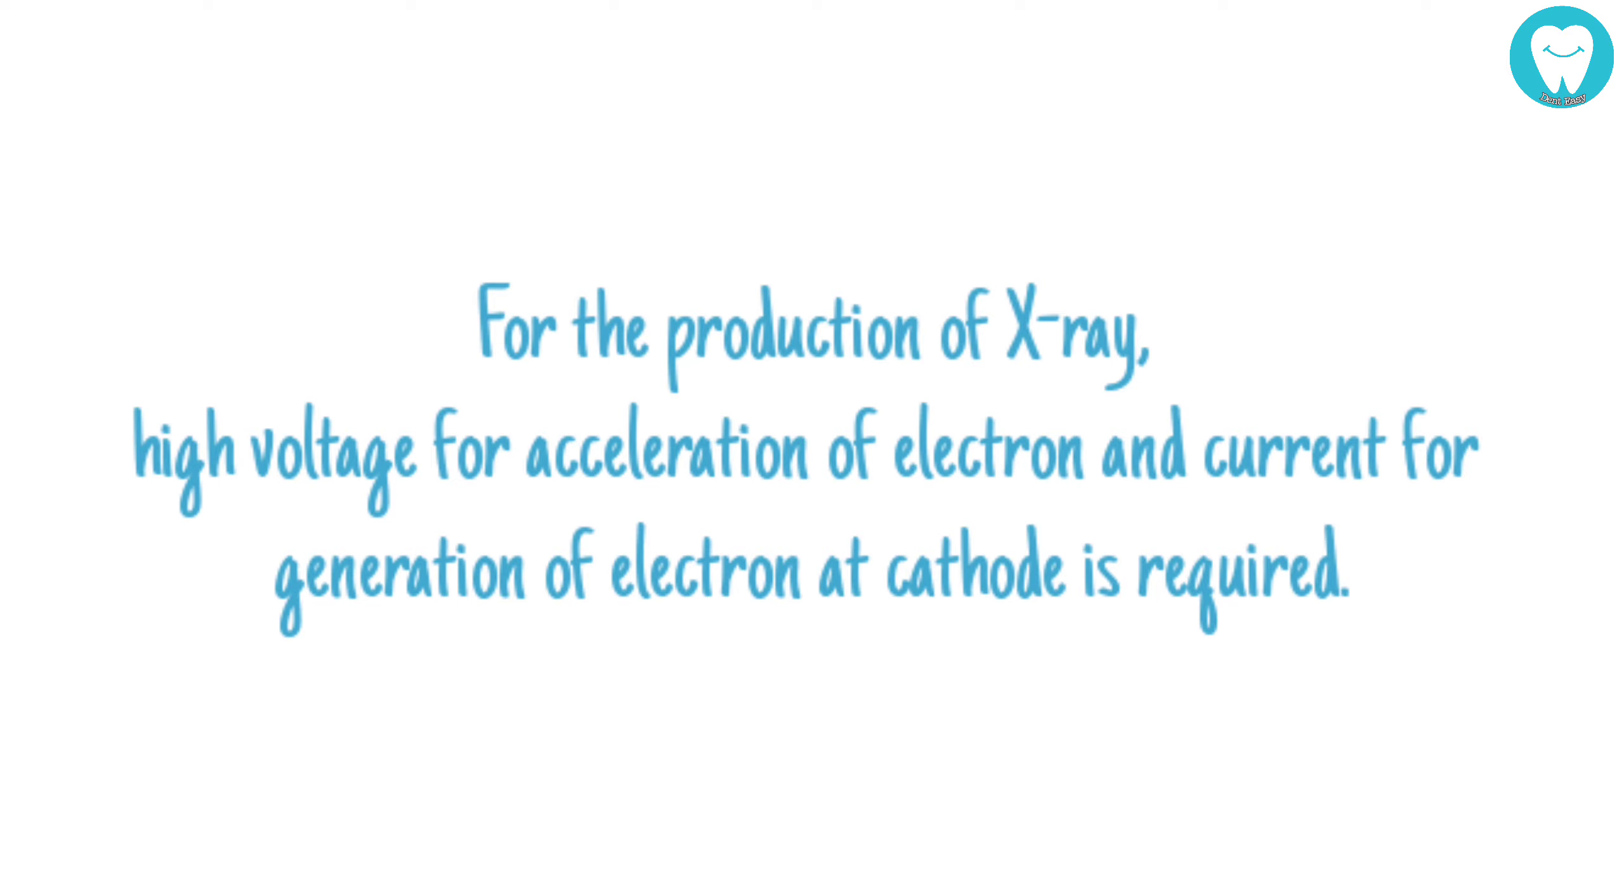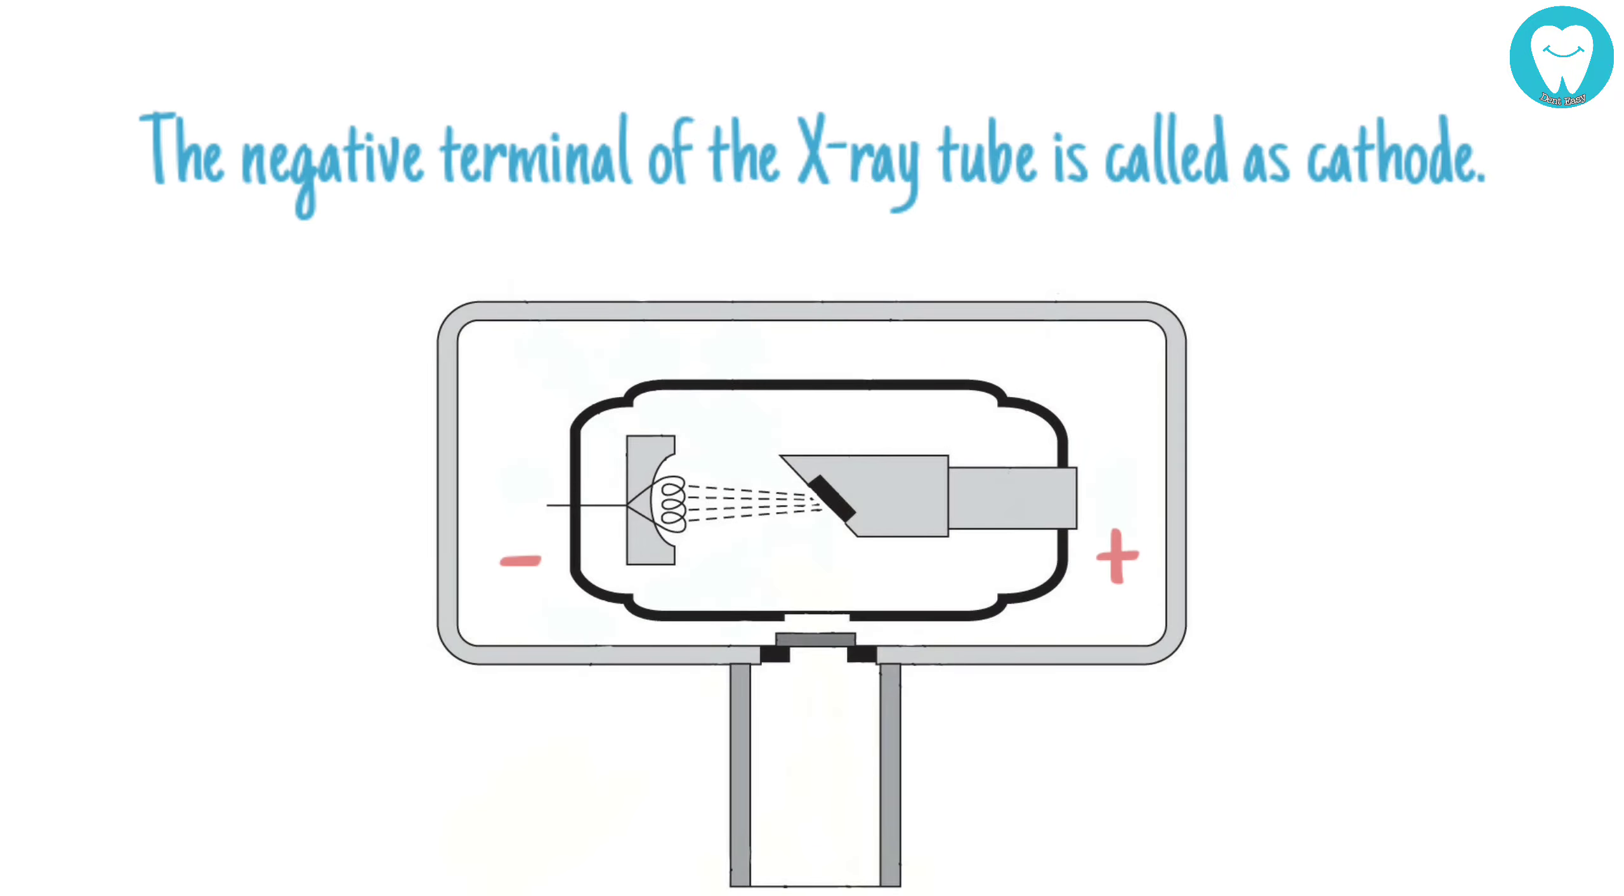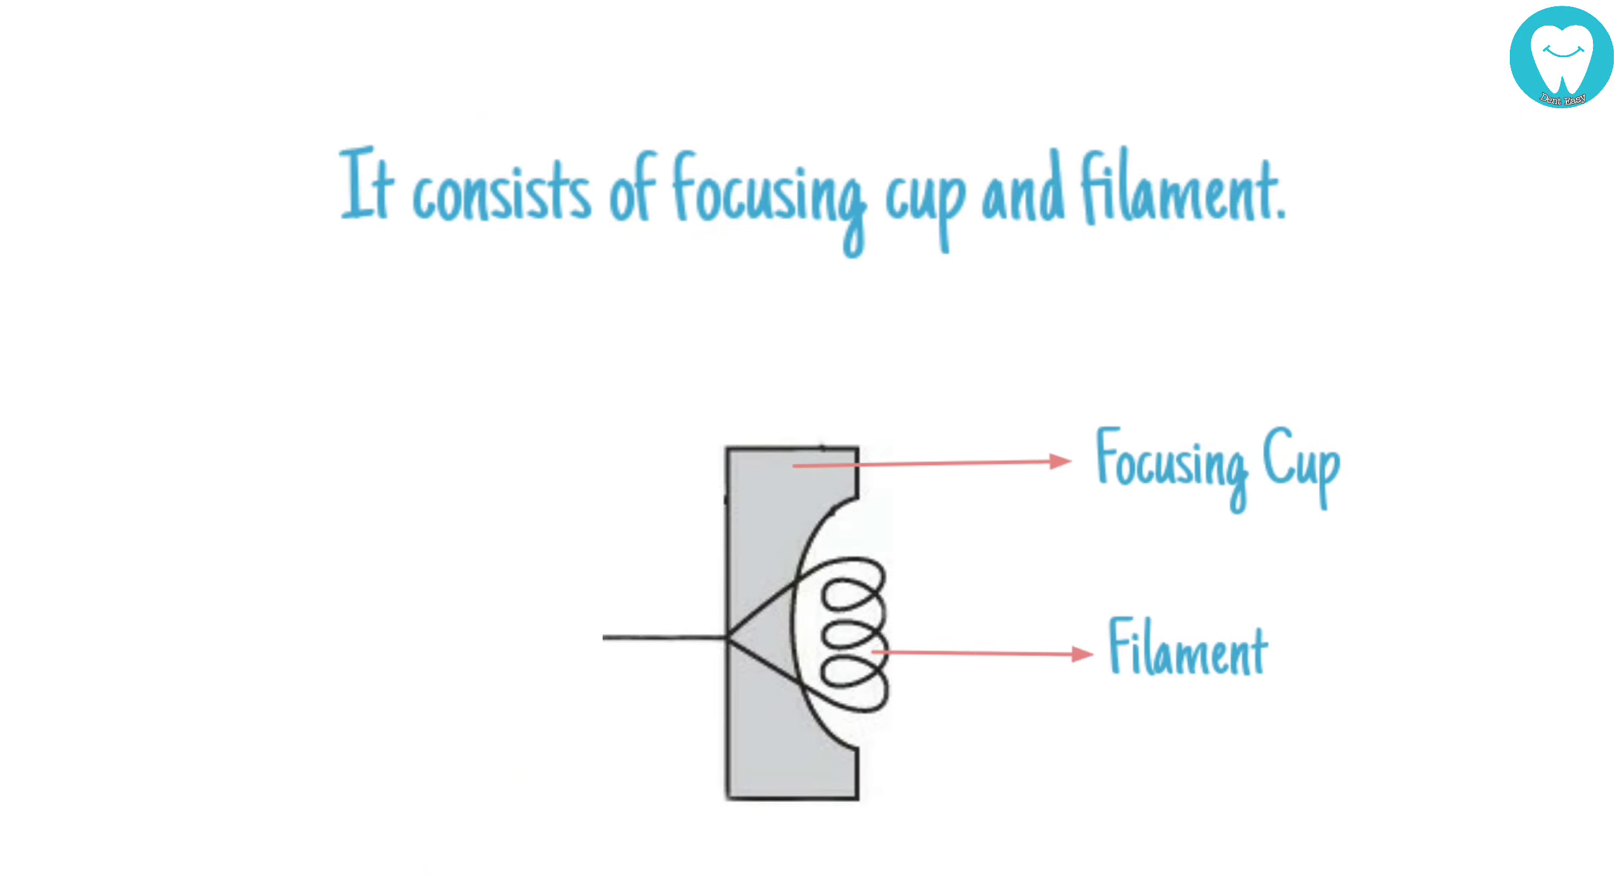Now let's take a look at the cathode. The negative terminal of the X-ray tube is called the cathode. The cathode is placed approximately one inch away from the anode and consists of the focusing cup and filament.